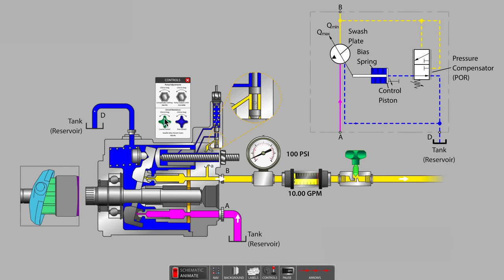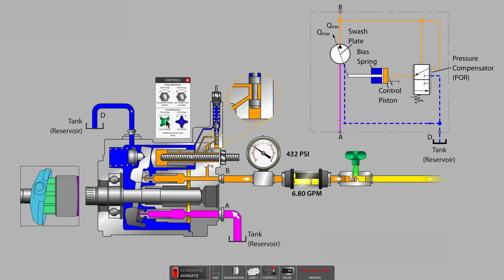Let's tighten the setting of the needle valve to cause greater circuit resistance. Naturally, this causes our system pressure to rise. Just after passing the 400 psi mark, we notice that the pump's pressure compensator has become active. Also notice that the swashplate is now moving and notice that the flow meter indicates less than full value.